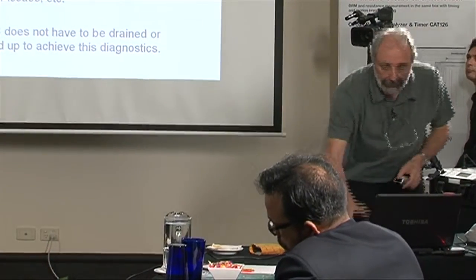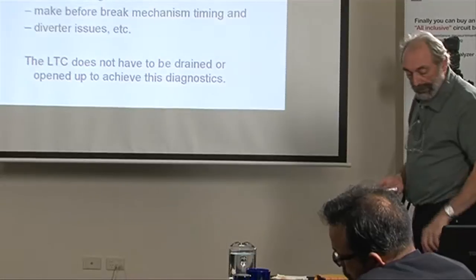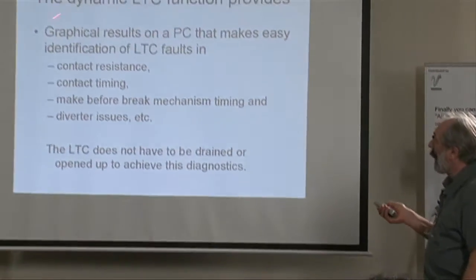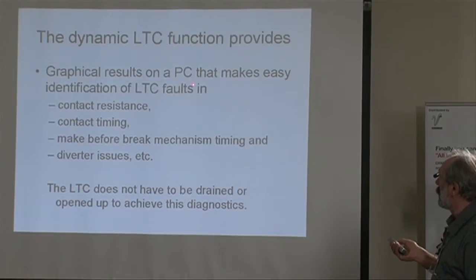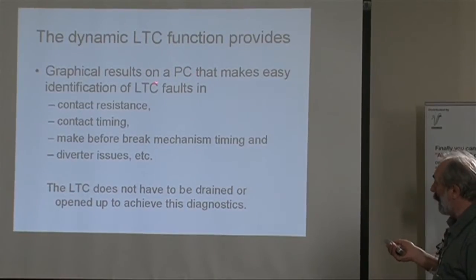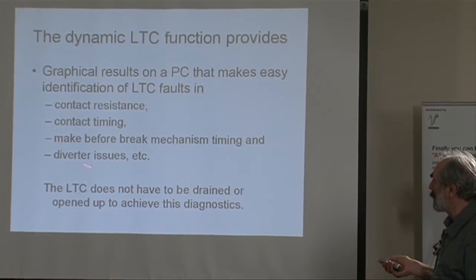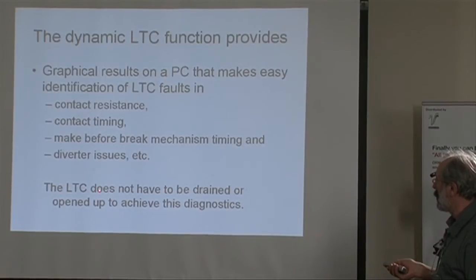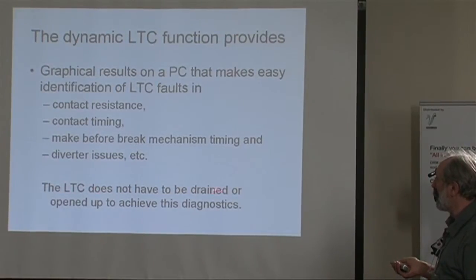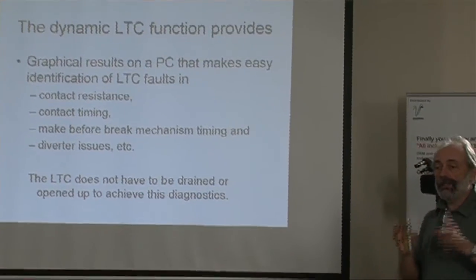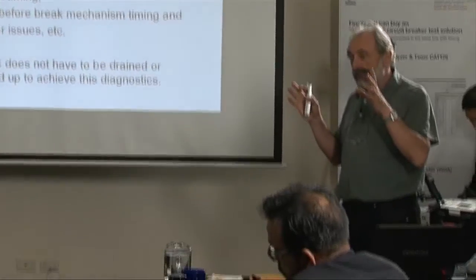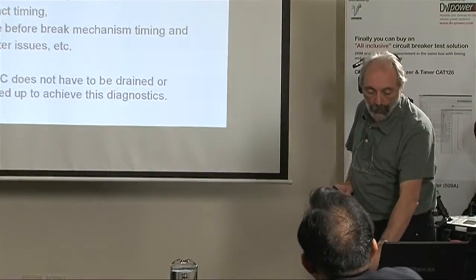What I like to point out is it's a graph that you can display on a PC. It helps detect various problems with the tap changer and the best of all is you don't need to drain or take out the tap changer. You do it as a simple winding resistance measurement with the fast recording.